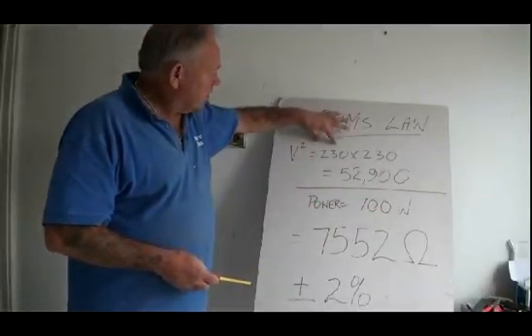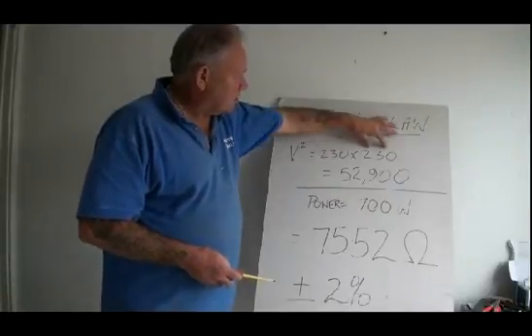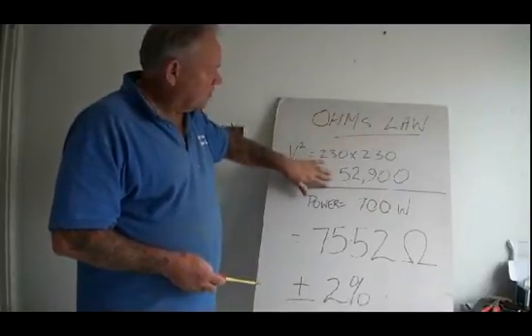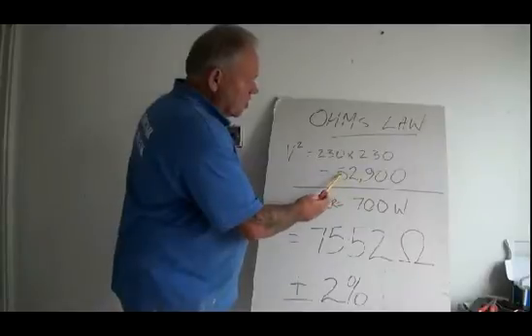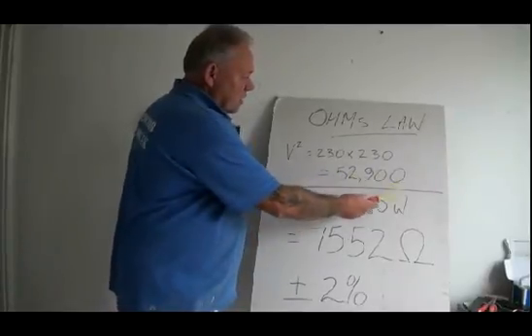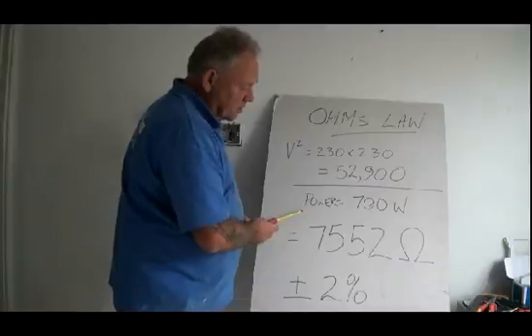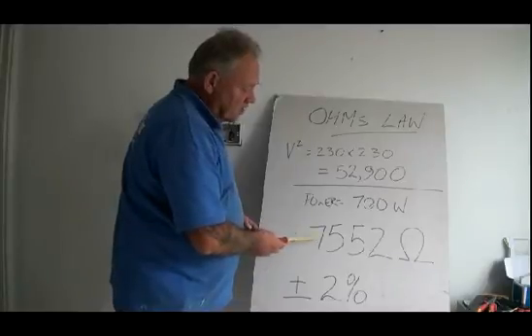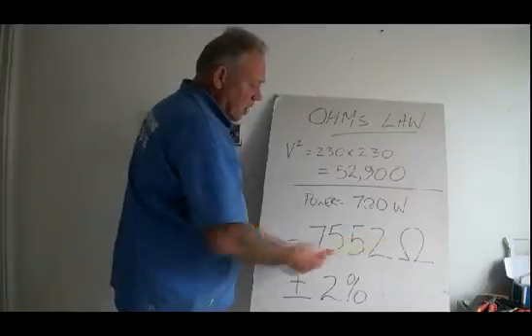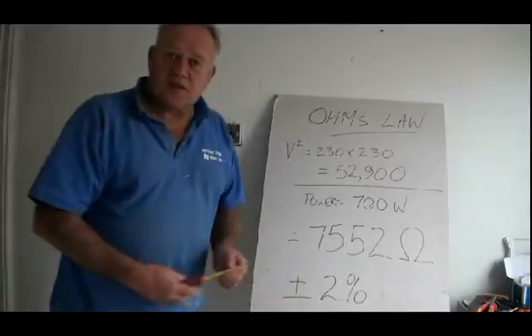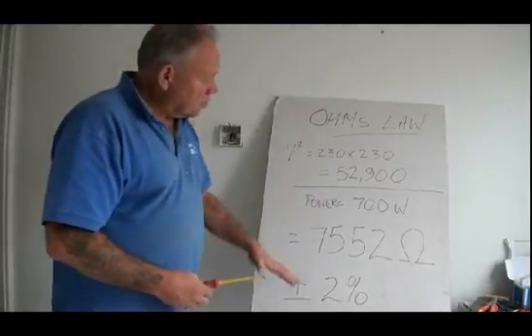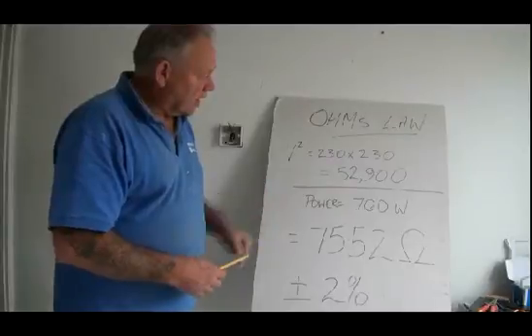Voltage is 230 volts. So voltage squared is 230 times 230, which comes to 52,900. We divide that by the power, which is 700 Watt, and we should get a reading of 75.52 Ohms, plus or minus 2%. So that is what we should get on our heating mat.